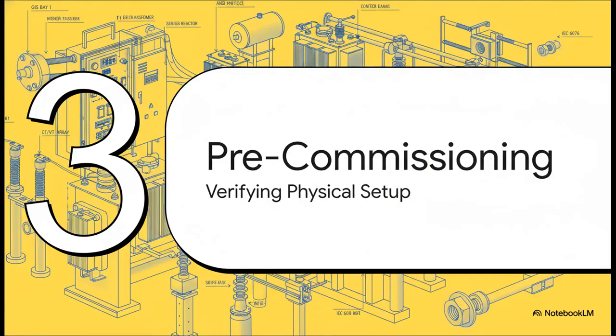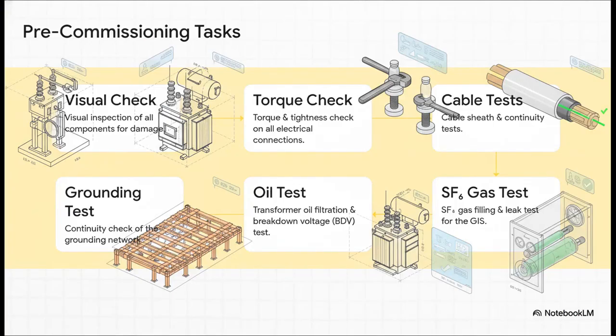Right, before even a single volt of electricity gets applied, the groundwork has to be absolutely perfect. This is the pre-commissioning phase. It's a hands-on, physical check of every nut, every bolt, every connection. It's all about making sure the physical construction perfectly matches the engineering design down to the last detail. And the key here is just painstaking attention to detail.